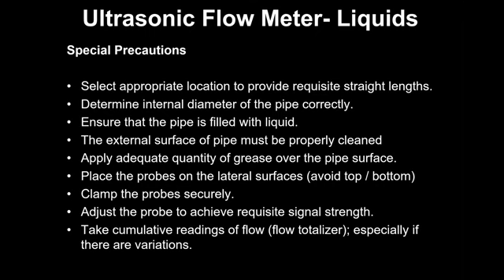These are the precautions. I think the first one I already discussed with you. The diameter has to be correct, of course, I said that. Then the pipe should be filled with liquid. This is very essential. Sometimes people have a tendency of taking the reading on a vertically down pipe which is falling in a cooling tower. If it is vertically down and connected to a continuous pipeline, it is all right, it will be filled. But if the liquid is falling in an open pit, then that pipe may not be filled with liquid.